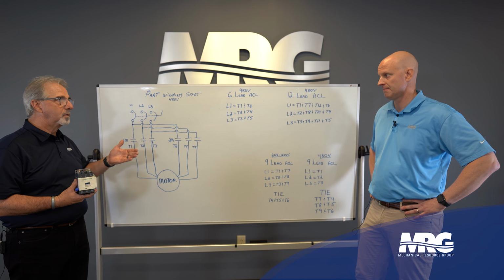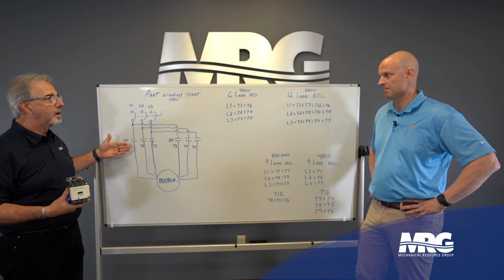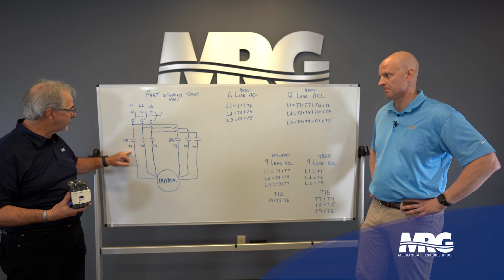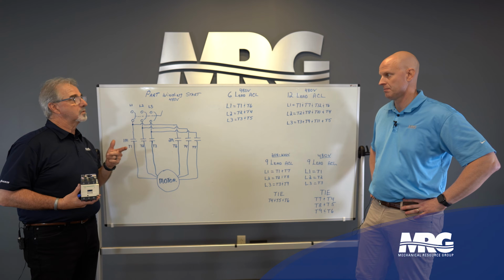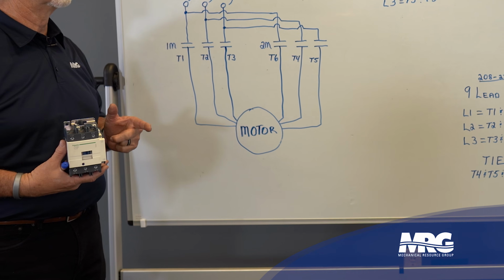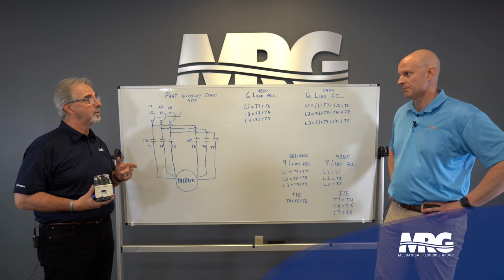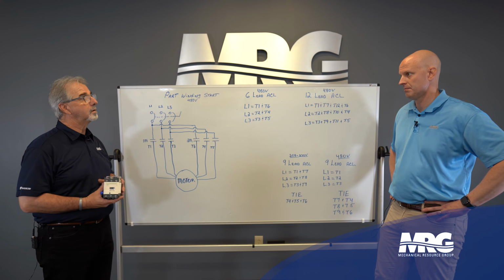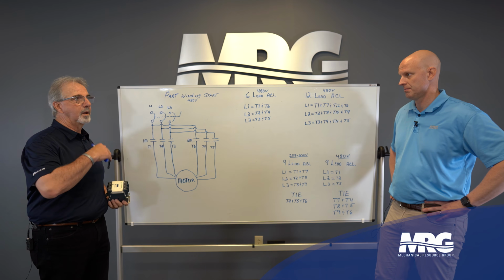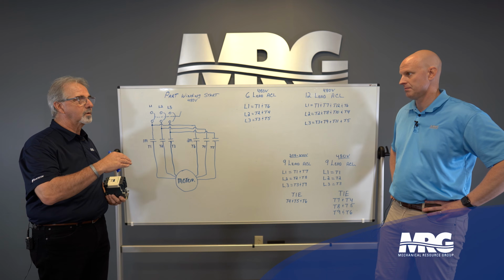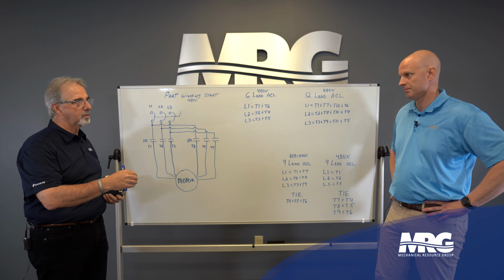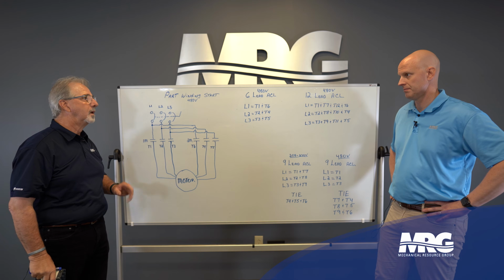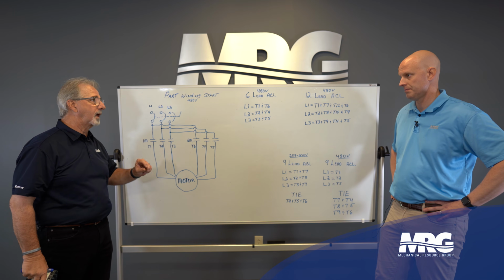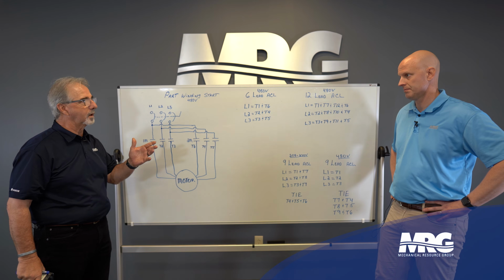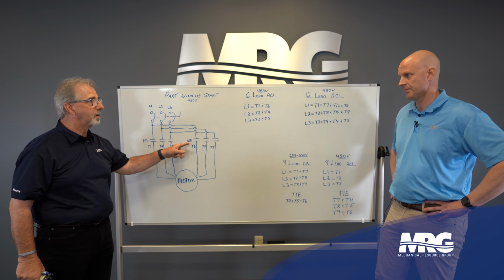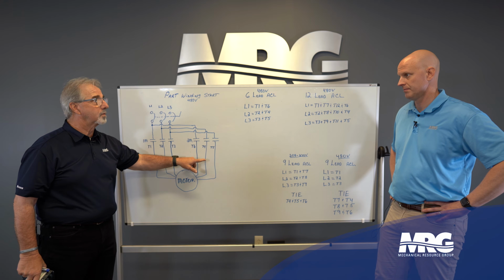Basically, when we do part winding start, the 1M contactor comes in first, and that connects my leads 1, 2, and 3. What that essentially does is give me 68% performance of that motor winding. I'm only using 68%, and I'm getting about 4 times inrush current. As soon as I see the inrush current start to drop off, a timer in the control circuit, which I usually set for 3 to 4 seconds, will close the 2M contactor and bring in the other side of my winding.